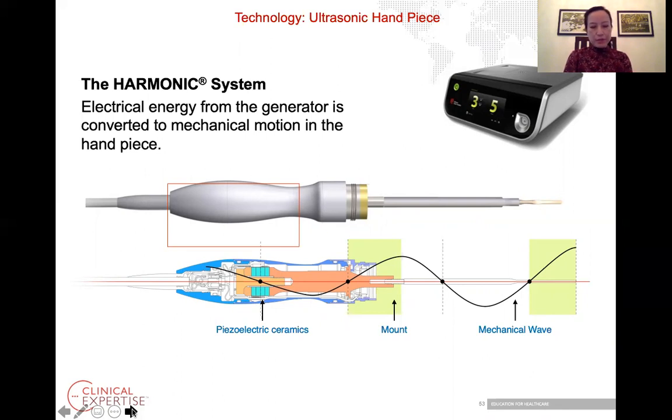When the blade is coupled with a tissue, it creates intercellular friction within the tissues, breaking down hydrogen bonds and resulting in protein denaturization and the formation of a sticky coagulum. Therefore, an ultrasonic instrument eliminates the risks of electrical injury to the patient and surgeon, since there is no current flowing through the patient.